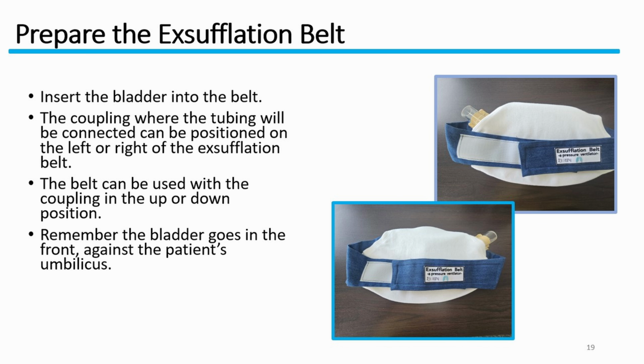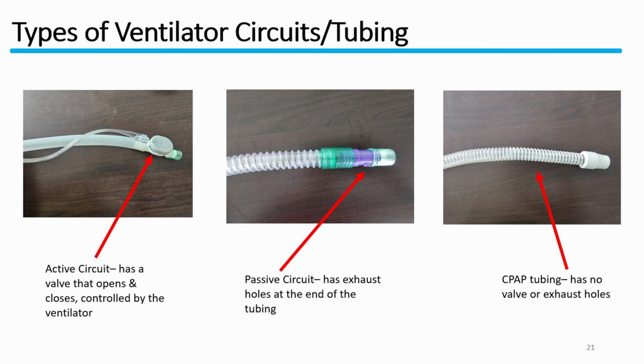If the patient does not have a ventilator currently, use CPAP tubing with a disposable exhalation port with the exsufflation belt. This is the easiest, least costly, and most durable. Types of ventilator circuits and tubing. All the different types of ventilators and ventilator circuits are compatible with the exsufflation belt. The important thing is to make sure that there is a way for the air to leave the bladder between breaths.